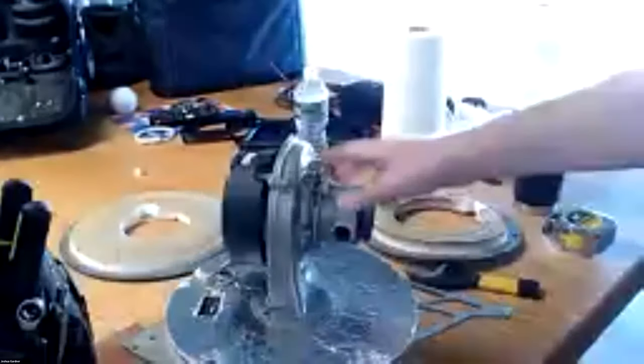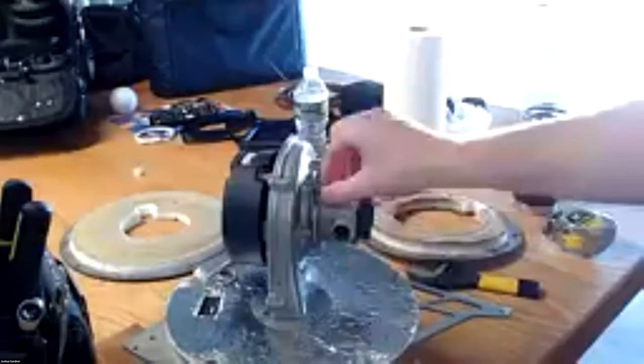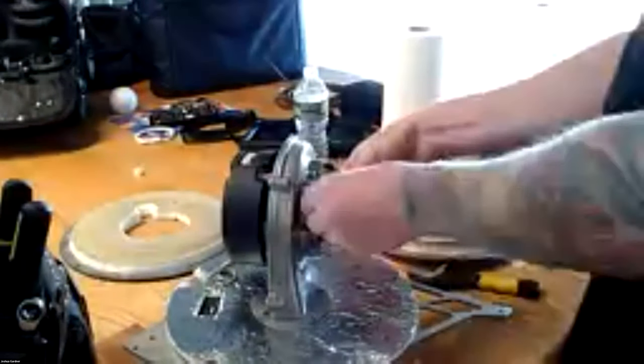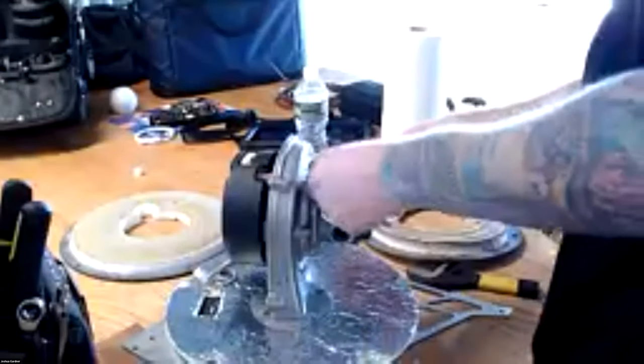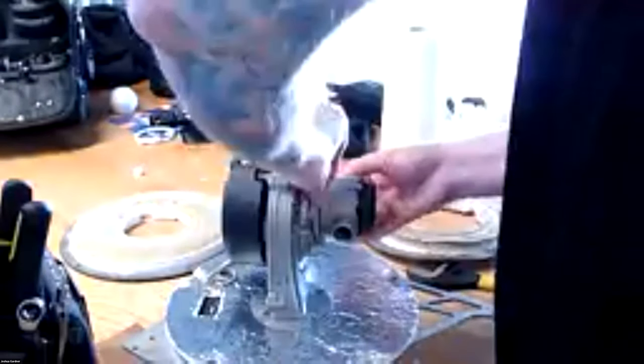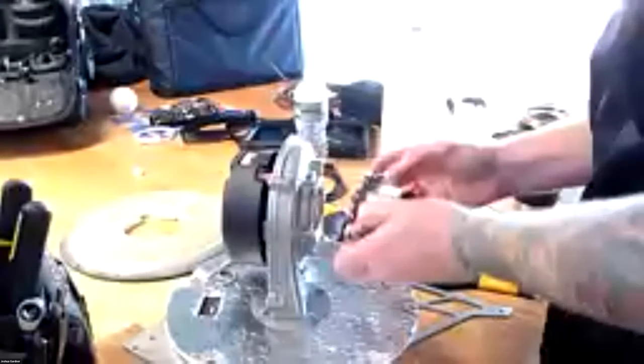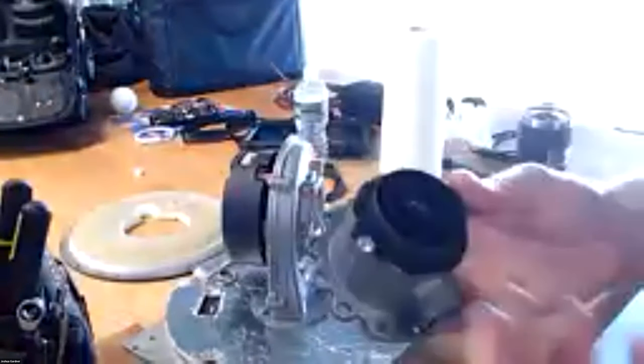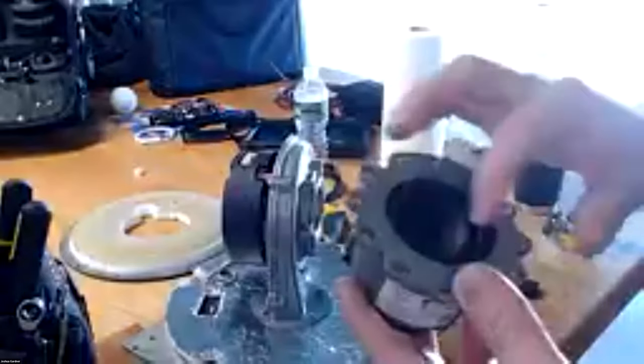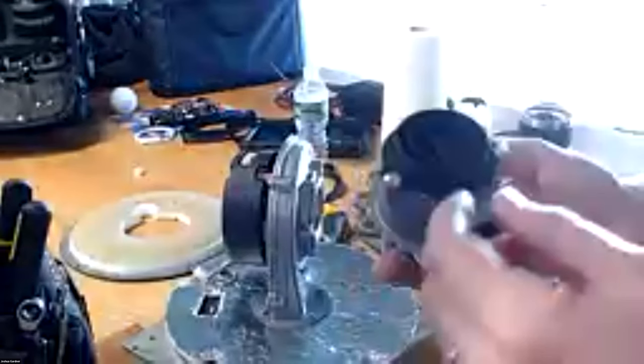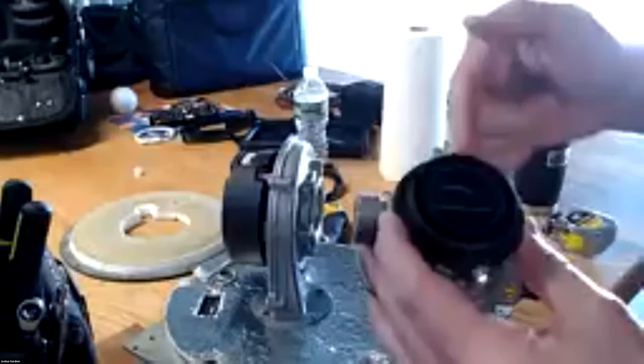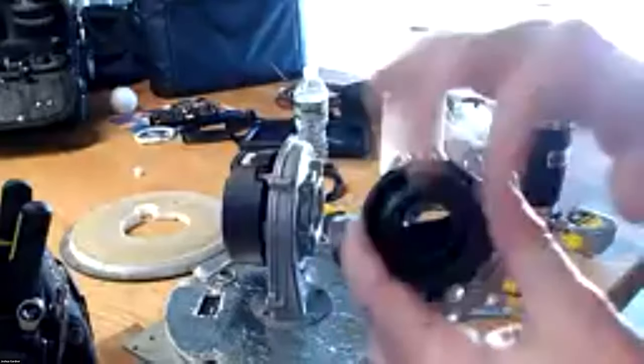You could pull the venturi if you wanted to, and you could take a look at the inside of the venturi. Because this is pretty much the point where if you've got crap coming in the intake, this is where it's going to get caught up. It's going to get caught up in the venturi. Also for cross-contaminating, this is where we're going to see signs of that. So you could pull the venturi, inspect it, make sure my flappers are working okay, nothing's broken, nothing's cracked up into this plastic. Those would all be pretty good indications if we're cross-contaminating.